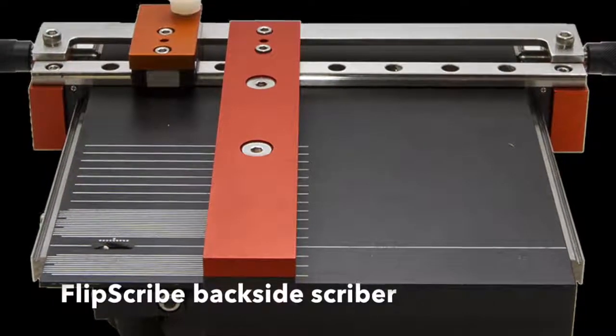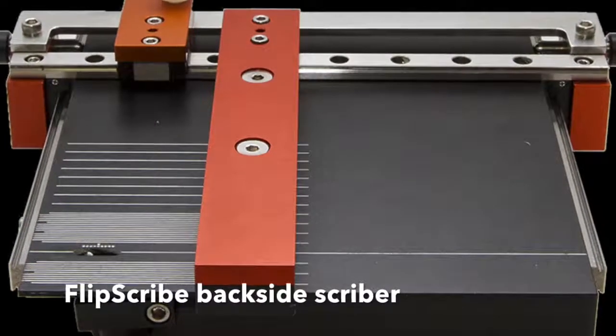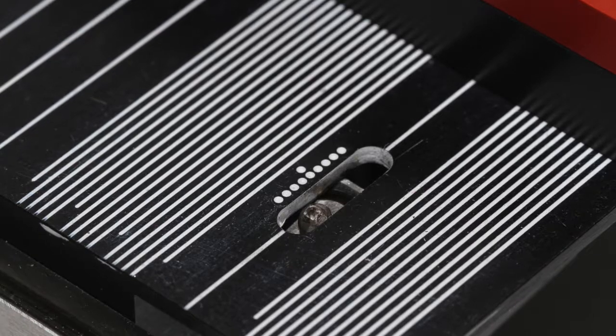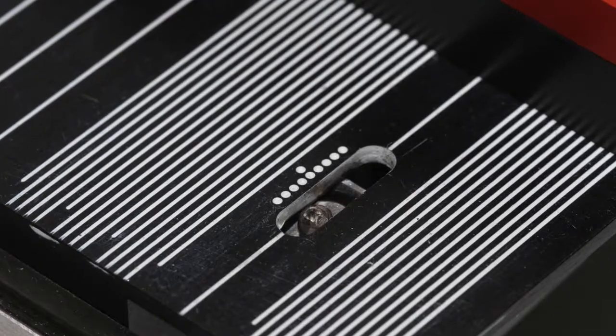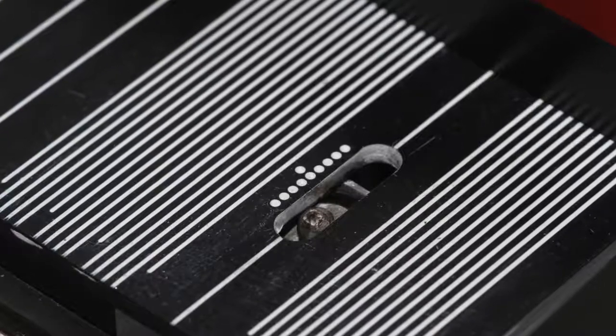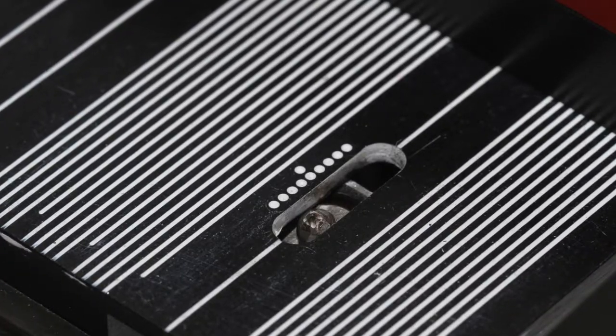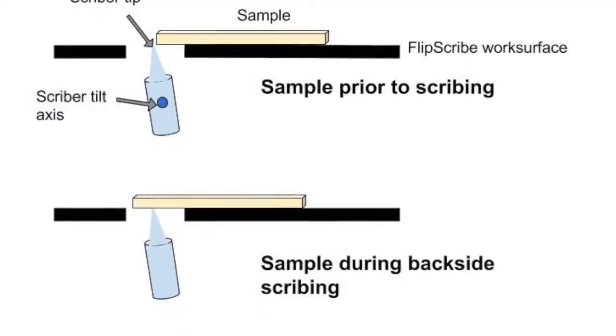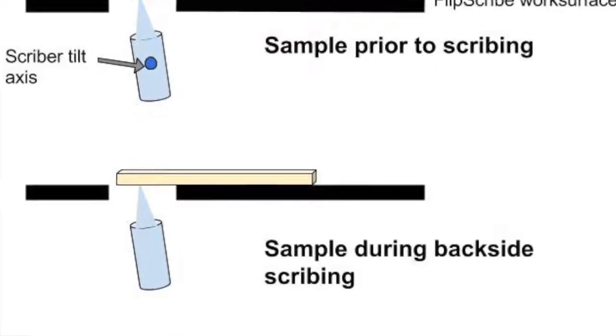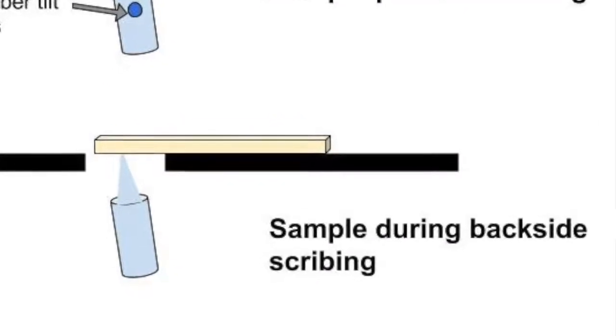This cleaving tool is novel in how it scribes the wafer. With the scriber embedded in the base of the tool, scribes are made on the back side of the wafer. This will preserve patterned material on the top side while placing a precise scribe underneath.